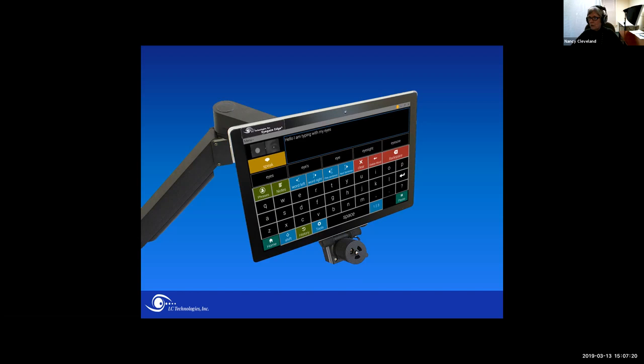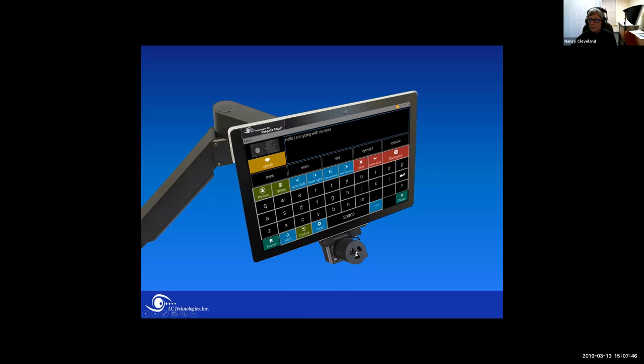We do something different than other eye tracking companies — we keep the camera separate. One of the reasons we do that is because we use a single source of infrared light on the user's eyes. Because I'm a nurse, I'm a patient advocate like no other, and I have real issues with how much light we put on somebody's eyes, particularly when the eye is the only method somebody has for communicating. So we have stuck with this idea of a single source of infrared light — one LED — to run the system for the whole history of the company.